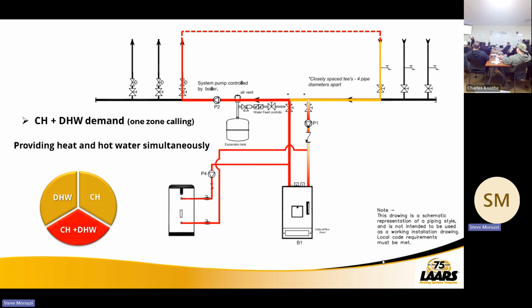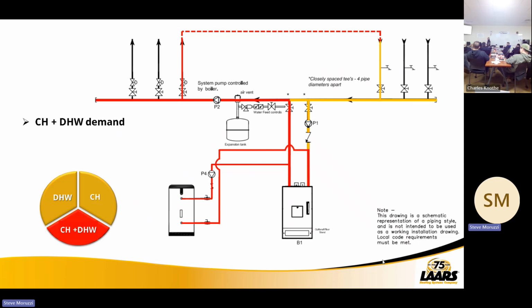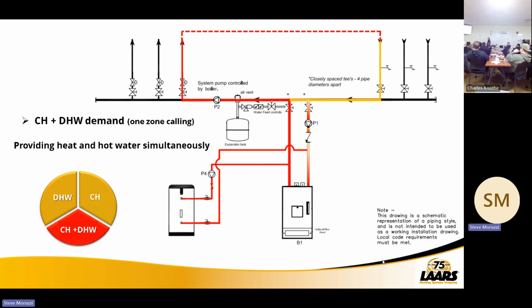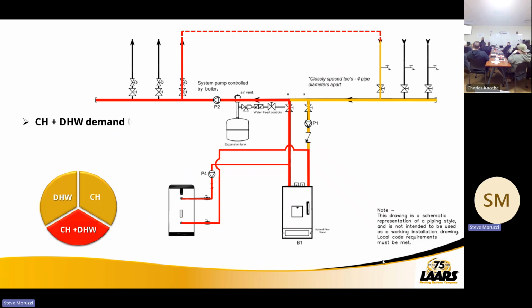So we'll energize the P4 pump, which is for the indirect tank. We'll pull also heat out to that indirect tank. And now if our modulation modulates up to 80% of modulation, so example here, let me go back. So we had one zone calling. So let's say a second zone calls or a third zone. And now we have a high demand.